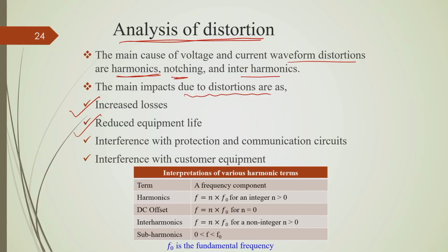But what will happen to this non power frequency periodic distorted component, we call them harmonic components. So, they will cause some extra losses, they will cause reduced equipment life, they will interfere with protection and communication circuit, they will also interfere with the customer equipment. And many times this customer, they generate harmonics and inject to the system. Okay. Now, these harmonics are, as I said, integer multiple of this fundamental frequency component, like n multiplied by f naught, where f naught is your fundamental frequency component, where n is an integer.